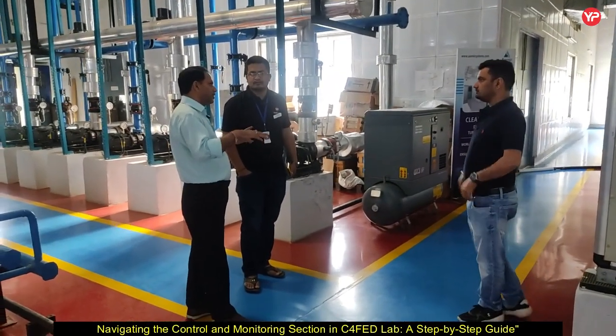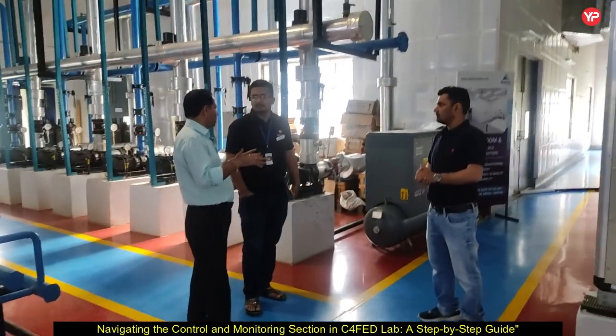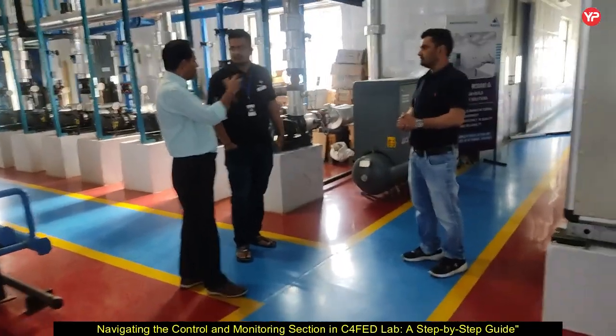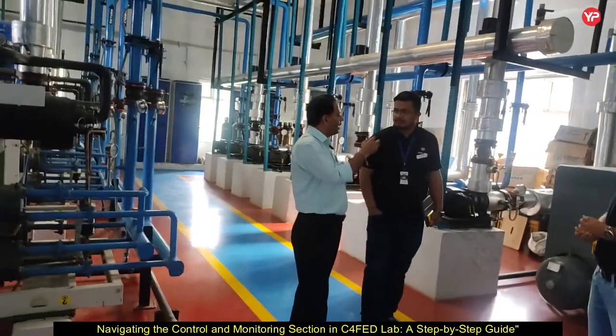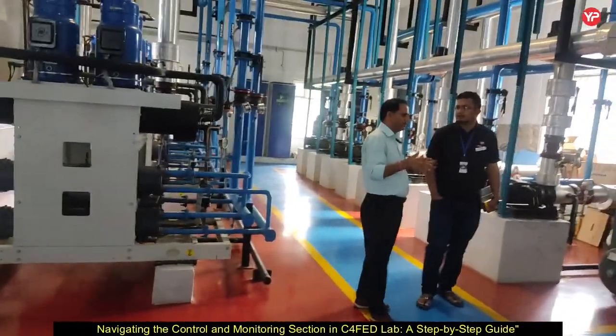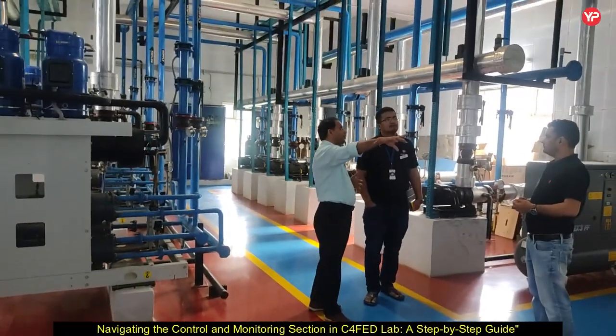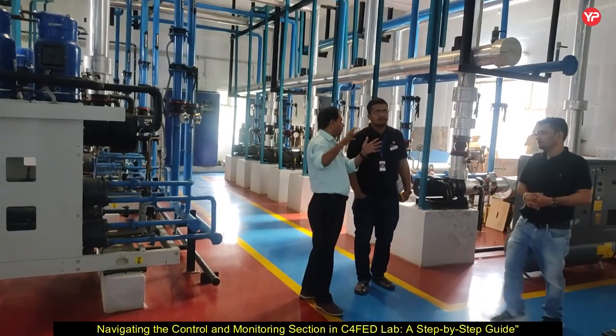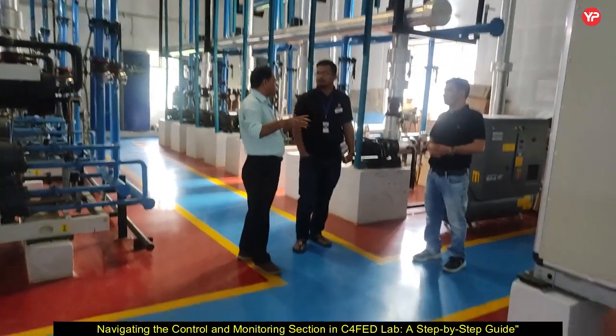That is basically class 1 lakh, meaning 1 lakh particles of 500 nanometers may be there. That is not that clean an area. So this AHU, the air handling unit, is for that small corridor, because it is not that clean.